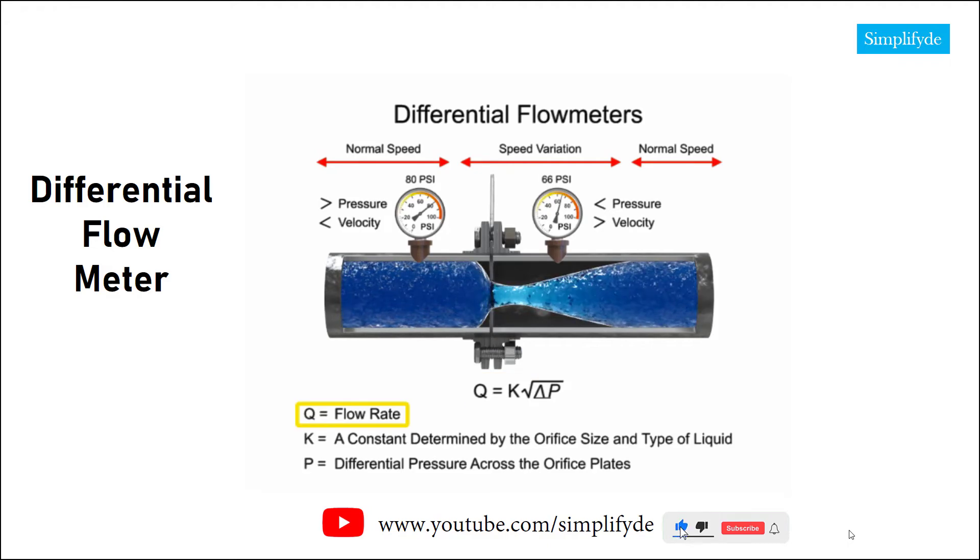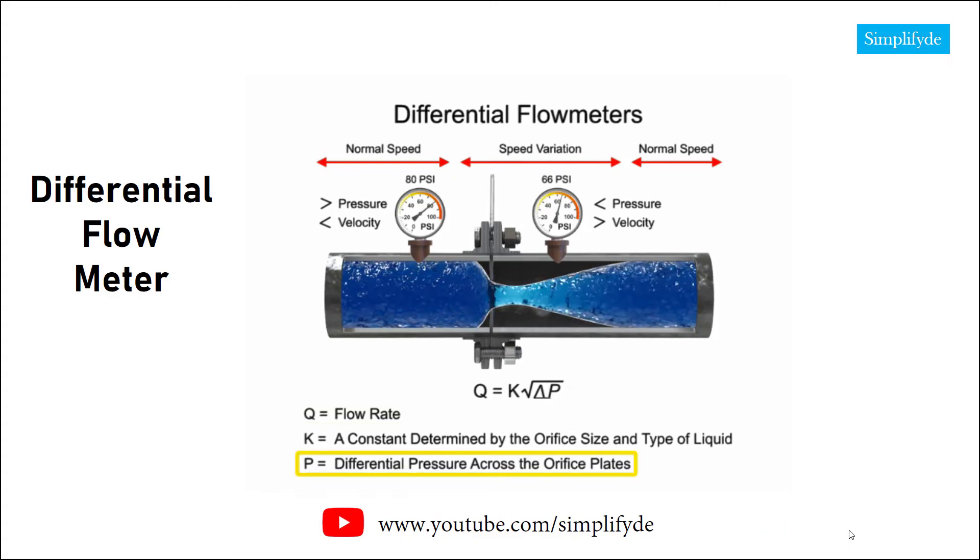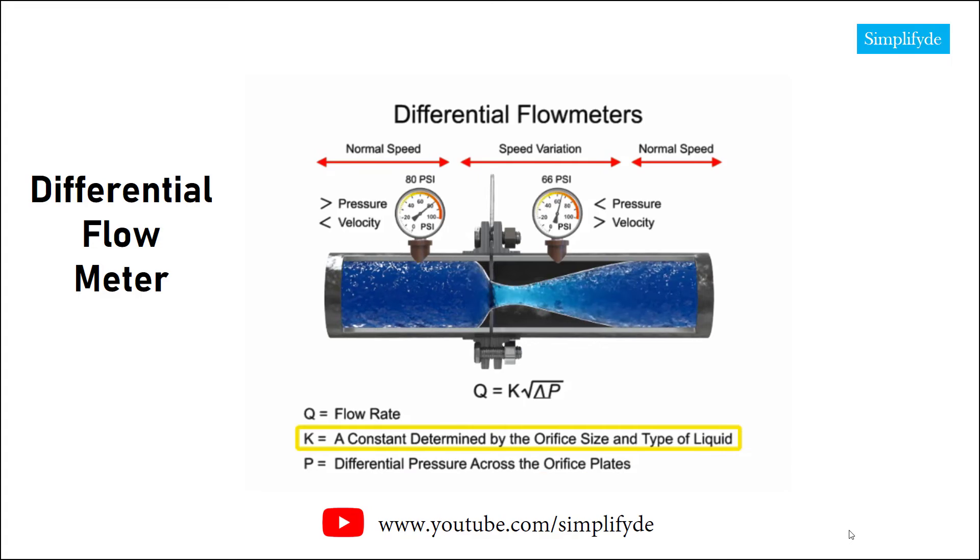The flow rate, Q, of a fluid through an orifice plate increases in proportion to the square root of the pressure difference on each side multiplied by the k-factor.